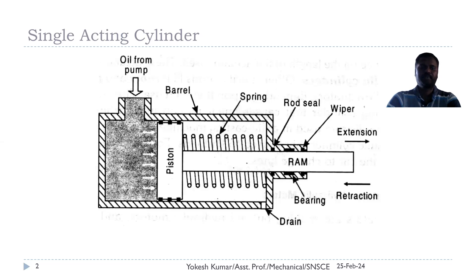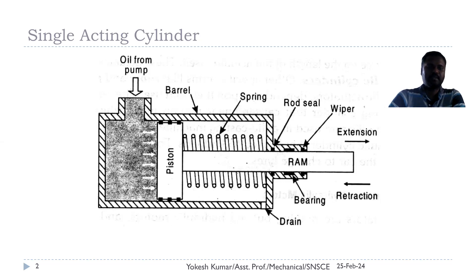Inside the barrel, we have a piston which is in close contact with the barrel or shell of the cylinder, operated to very close dimensional tolerances. The piston diameter is slightly less than the inside diameter of the barrel — a small clearance is provided to enable linear motion of the piston. There may be a chance of oil leakage past the piston, so to avoid this, the piston is surrounded with oil seals which prevent leakage of oil.